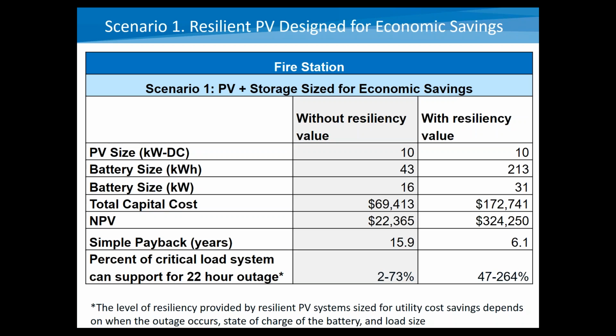The capital cost increases as well, because you're now paying for that larger battery, but the net present value is much higher. And the primary reason for that larger net present value is that now you are offsetting some of those grid interruption costs, because this system can save some of those costs for you by providing power during the outage. And so by avoiding those costs of grid interruption, you now have a much higher net present value, so a savings of about $324,000 over the 25-year life cycle of the project. And you'll see that the simple payback goes down quite a bit as well, to about 6.1 years.